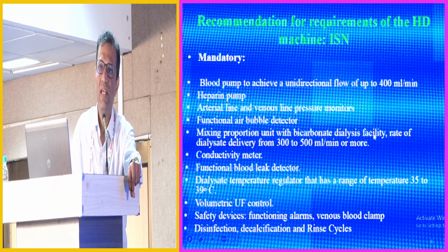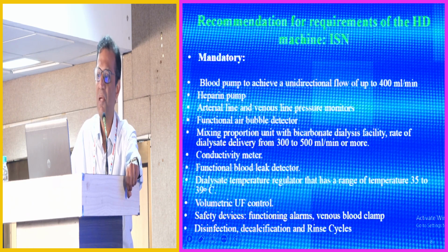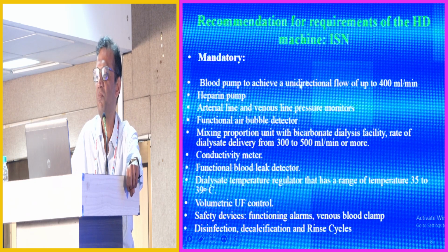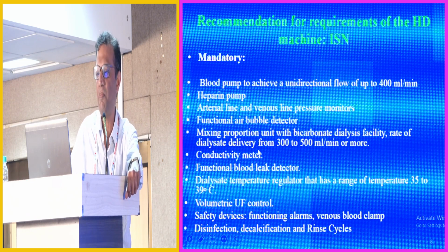So the ISN says that any dialysis machine must have certain mandatory requirements. So the blood pump must be able to deliver blood flow at about up to 400 ml per minute. As I said, it needs to be anticoagulated. It should have arterial and venous pressure monitors. It should not allow an air embolism, so there should be an air bubble detector.